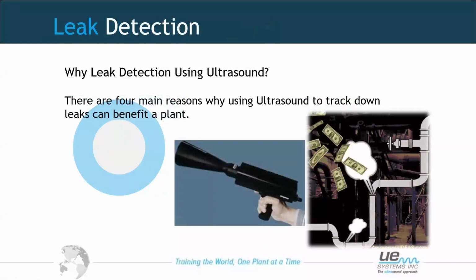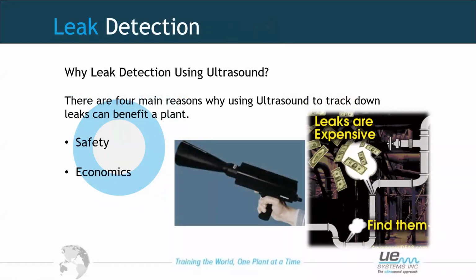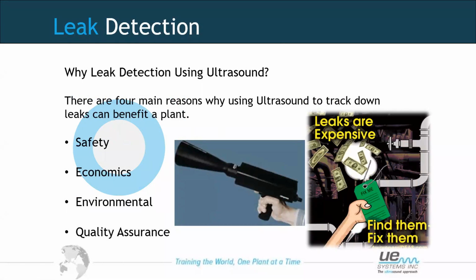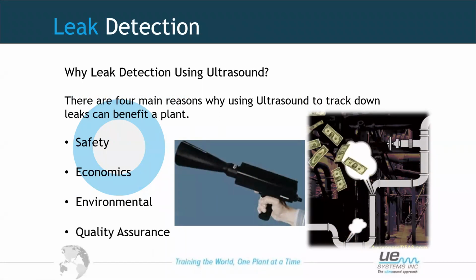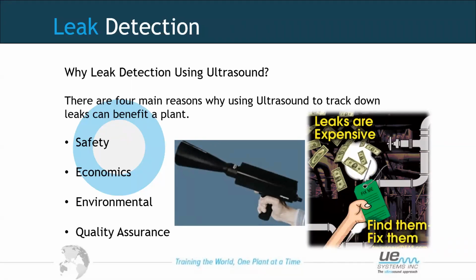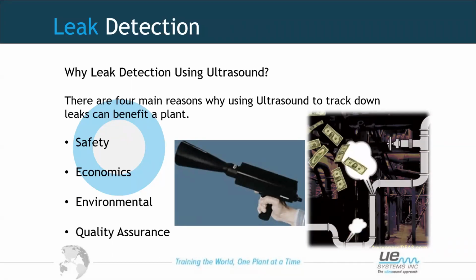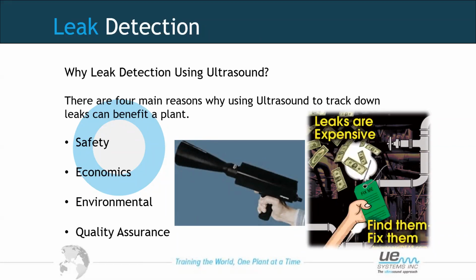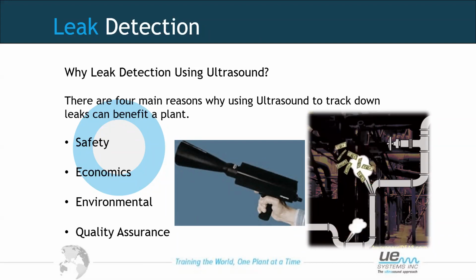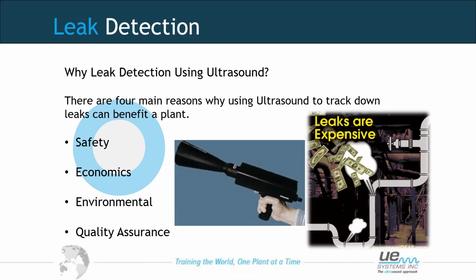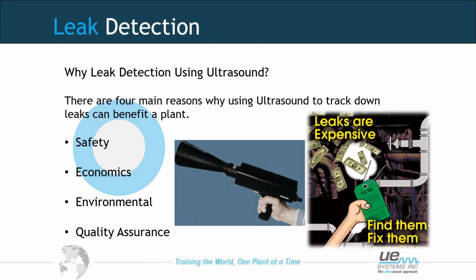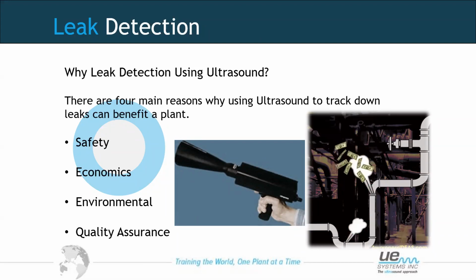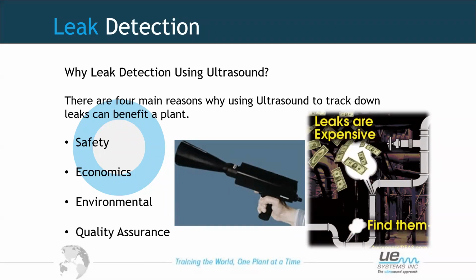There are four main reasons behind using ultrasound to help us track down leaks that can benefit our plant. The first one being safety. If we think about compressed gases, it's a pressurized system just wanting to normalize the pressure with the outside environment. It's like a bomb waiting to go off. That's very fragile structures. Also thinking about certain dangerous gases that we don't want to have a leakage that could cause fires, for example, or safety issues to our employees.